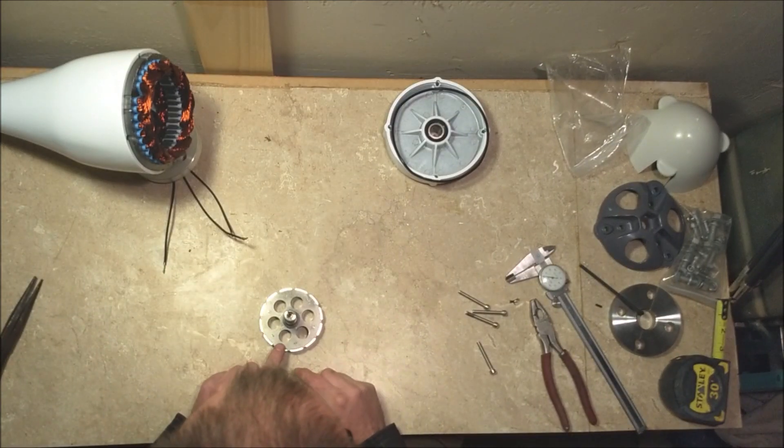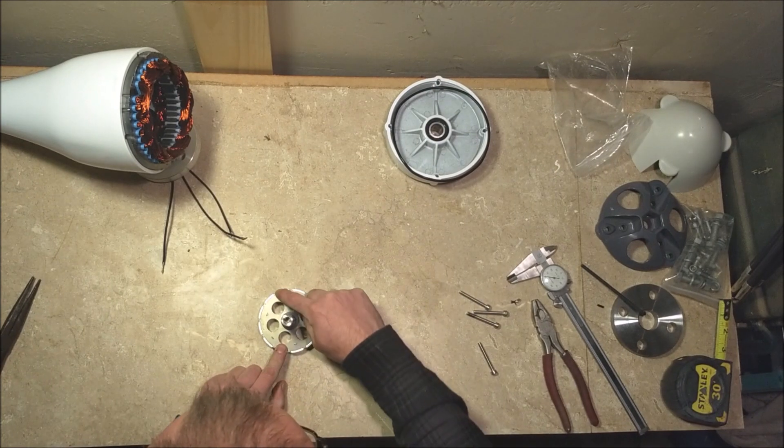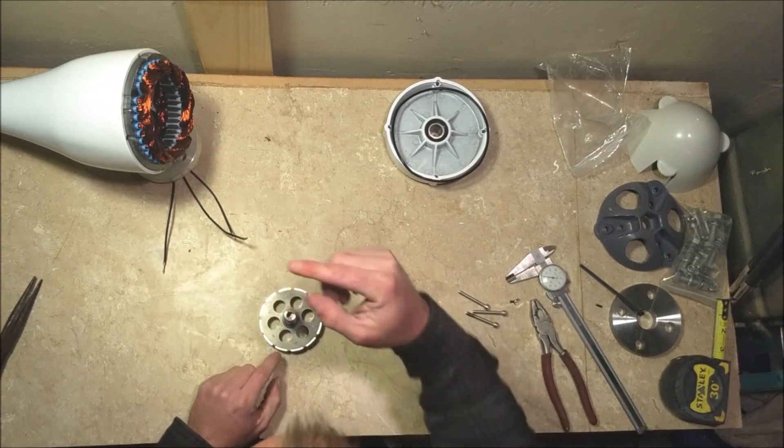The same thing with this rotor. One, two, three, four, five, six, seven, eight, nine, ten, eleven, twelve. Thirty-six coils, twelve poles.